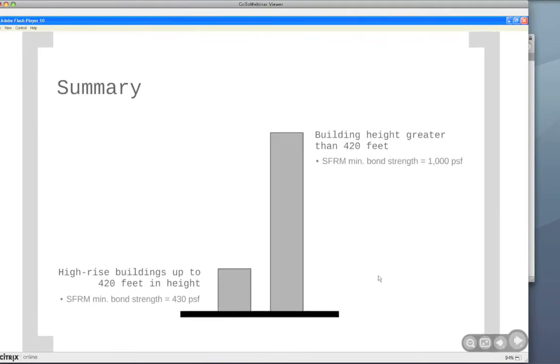for high-rise buildings up to 420 feet in height, the minimum bond strength for sprayed fire-resistant materials is now 430 PSF. And for buildings with a height greater than 420 feet, the SFRM minimum bond strength is increased significantly to 1,000 PSF.